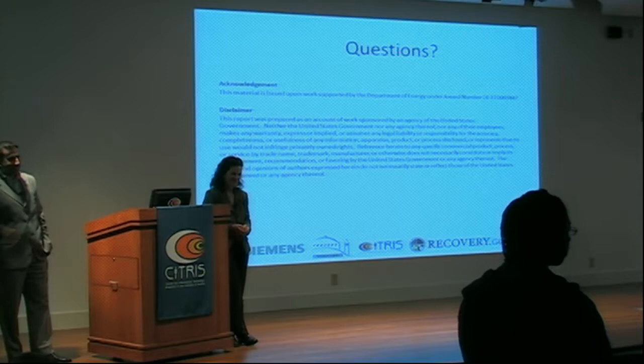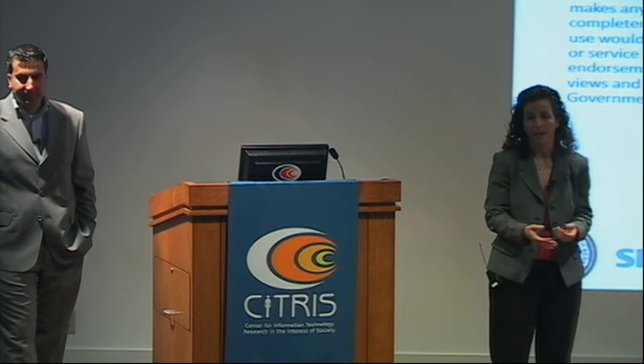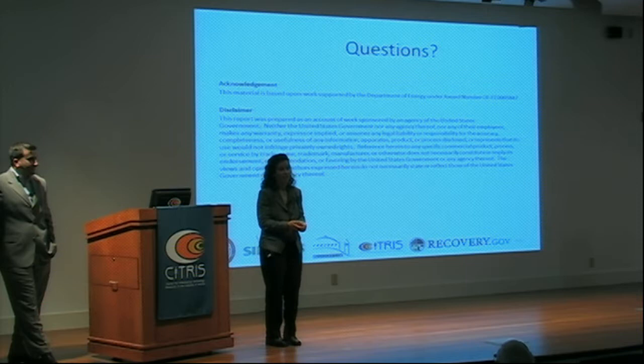Question: Do you have CO2 sensors? Most buildings are over-ventilated, so CO2 sensors could improve energy efficiency and be used during demand response events. Response: Yes, and we're working on it. We are running a test on one floor with CO2 sensors and running a survey at the same time to see if people detect a difference as we reduce ventilation levels. The ventilation rates do seem to be about three times the ASHRAE standard rate. It's not just about CO2 — there's air mixing, odors, and other issues — but Jay is working on establishing a network of CO2 sensors in the building. Good point; that's one of the things we're looking at.